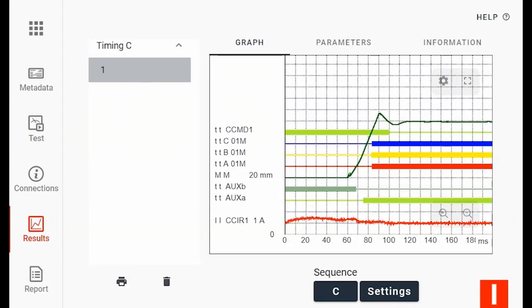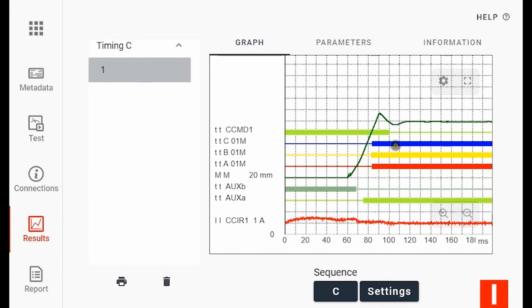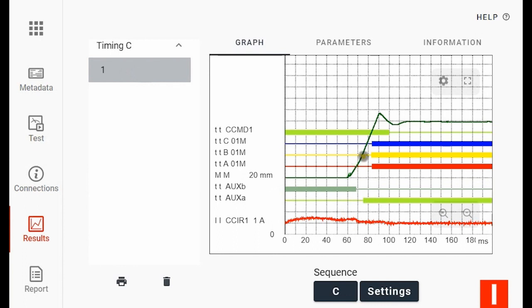Here I have my result as a graph. I have my coil current at the bottom, a very low current. I have also my timing traces, red, yellow, and blue. And I have my auxiliary contacts in green and I also have my motion measurement in green.